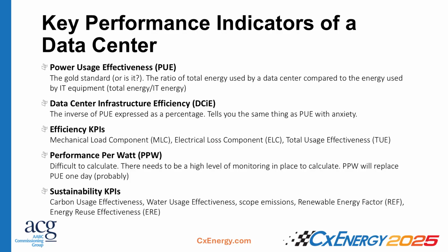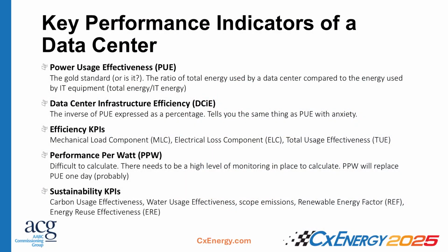Since the early 2000s, PUE has been the gold standard. PUE is power usage effectiveness, the ratio of total energy used by the data center compared to the energy used by the IT equipment—total energy divided by IT energy. It's always greater than 1, and like golf, lower is better, so you want to get as close to 1 as possible. New data centers are coming in very close to 1, which is why PUE in new construction is becoming less of a focus. The owner's not going to accept a PUE of 2, 4, or 8 if you commission the data center and say, here's the PUE, it's 1.79—that's not acceptable.